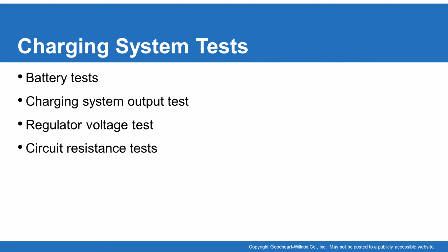Is the voltage stable where it's supposed to be? Is it able to compensate for any loads that are added to the system? Is the circuit resistance that is available within the specification, meaning that between the wires, do we have excessive resistance? Sometimes we'll see corrosion build up internally on some of these wires, and that corrosion adds additional resistance to the wire that should have very little resistance involved.